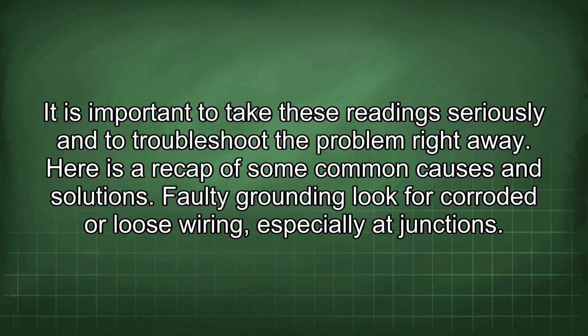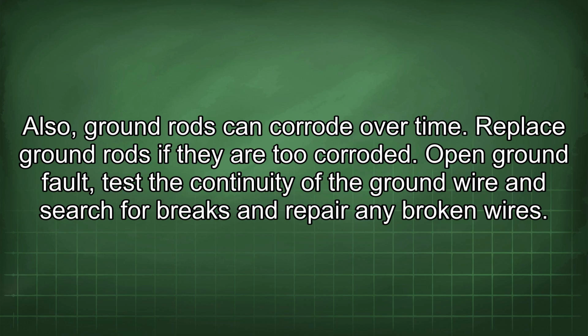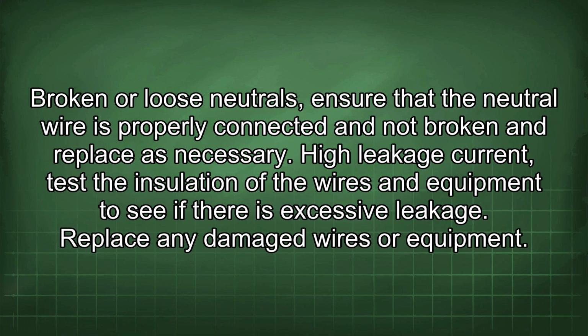Faulty grounding. Look for corroded or loose wiring, especially at junctions. Also, ground rods can corrode over time. Replace ground rods if they are too corroded. Open ground fault. Test the continuity of the ground wire and search for breaks and repair any broken wires. Broken or loose neutrals. Ensure that the neutral wire is properly connected and not broken and replace as necessary. High leakage current. Test the insulation of the wires and equipment to see if there is excessive leakage. Replace any damaged wires or equipment.